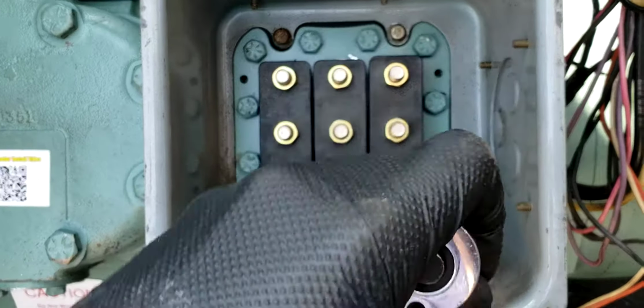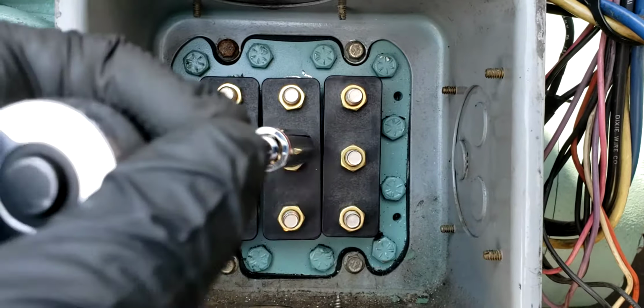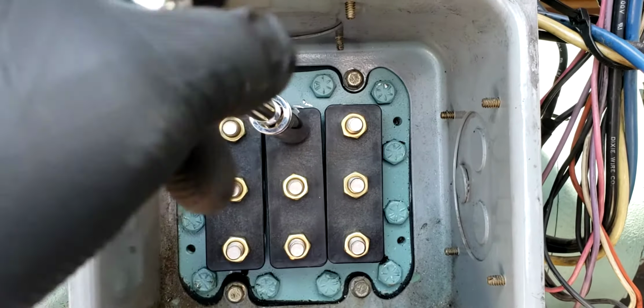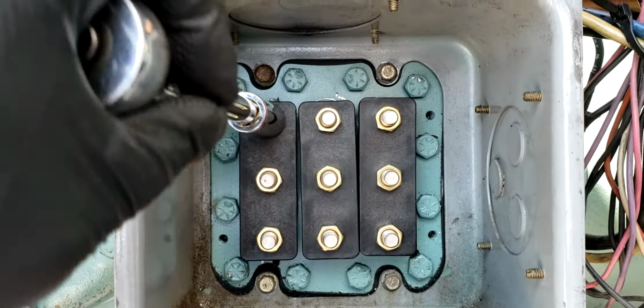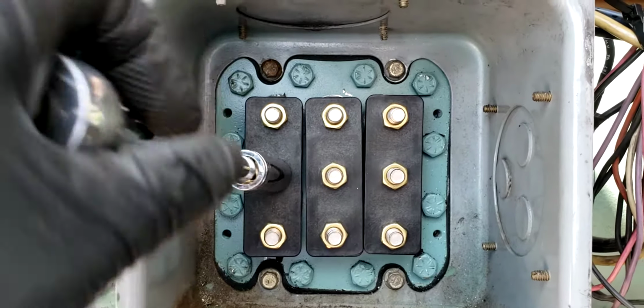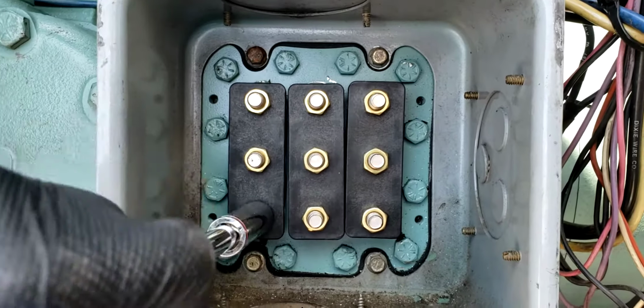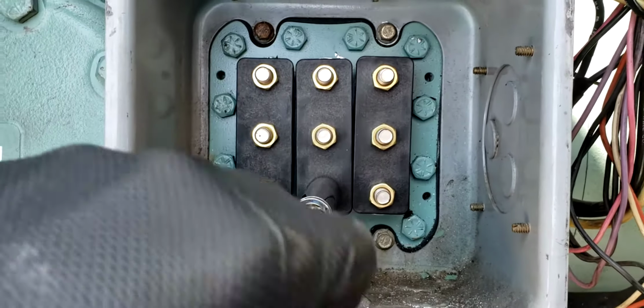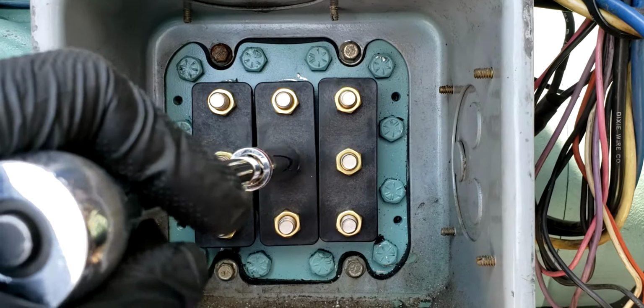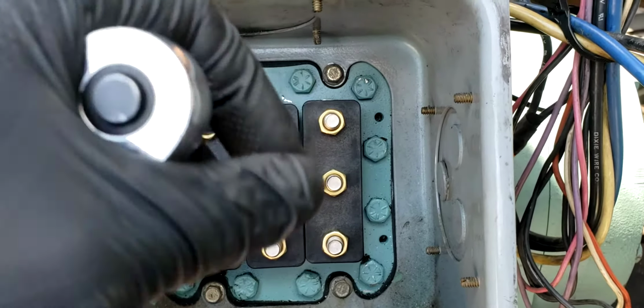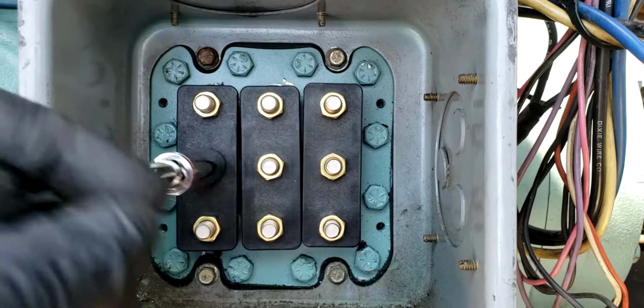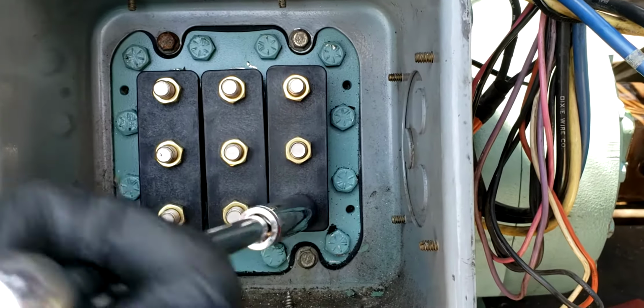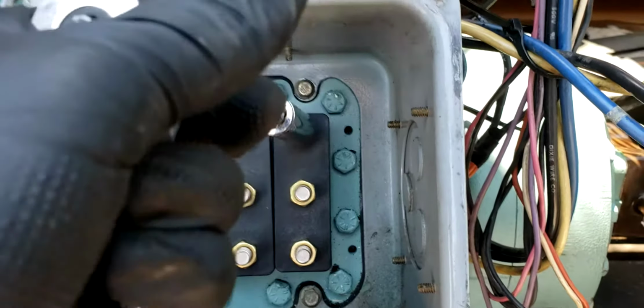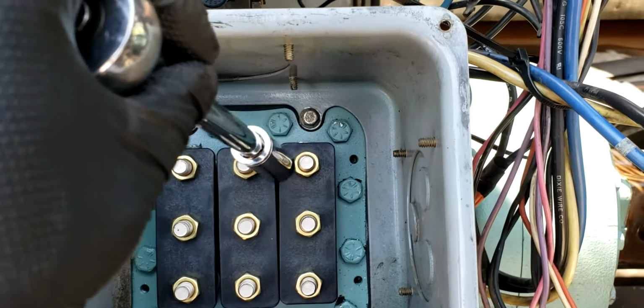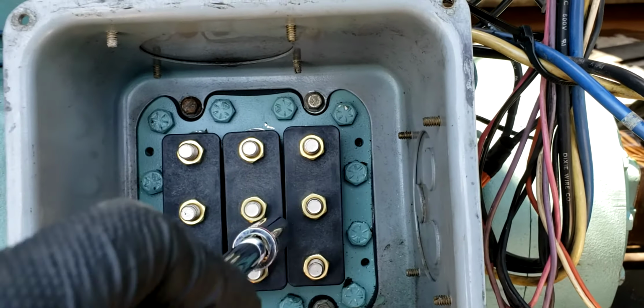Tighten them down, not too much - you don't want to break the plastic. First you untighten, then use your socket, don't go too crazy on that. You just want to hold the plastic in place so you can install your shunts and power supply wires, and lock those in. So long as they're snug, not too tight - you can see I'm just barely pulling on those, making sure they're all snug and everything is nice and level and flat. That's it, very little torque needed. If you go too tight, you'll see these things start to bend - the plastic. This one's a little bit nuts, but it's alright.